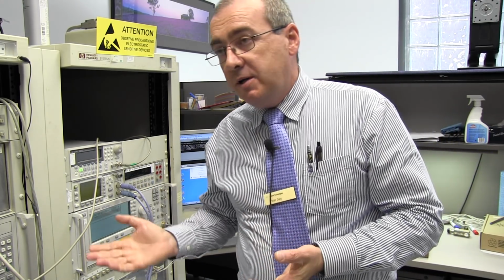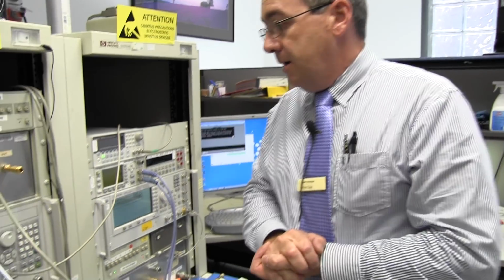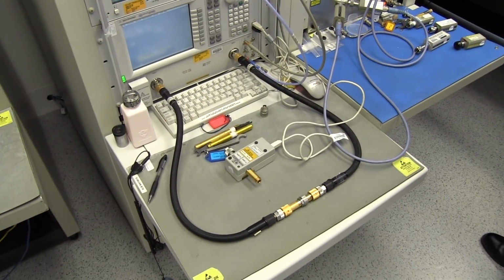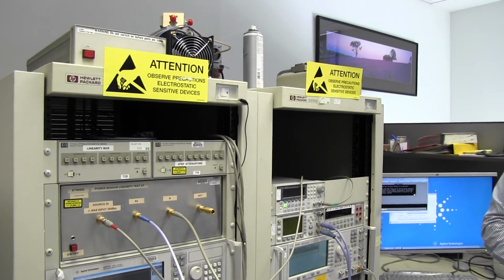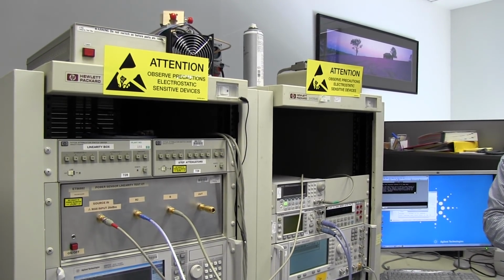Right. We haven't gone into X parameters in Australia. We haven't had a need to. We can provide the calibration and traceability for X parameters, but our devices don't need X parameter testing. So we are purely accredited for S parameters in that range. Excellent. All right. And that's $400,000 worth of kit just to calibrate. That's right. And there's a bit of science behind it as well.